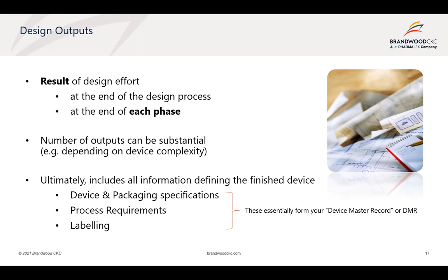Design outputs are a mandatory step in the design control phase, and the design control procedure you've got in place needs to define what those outputs are going to be. The outputs need to allow demonstration of product conformance to the input requirements you've defined, so typically you'd require some form of traceability from the output back to the input requirements of your design.